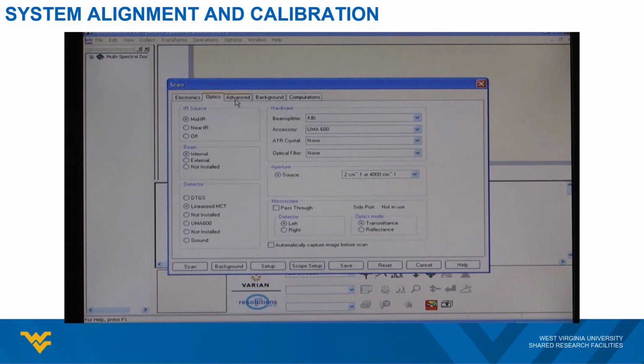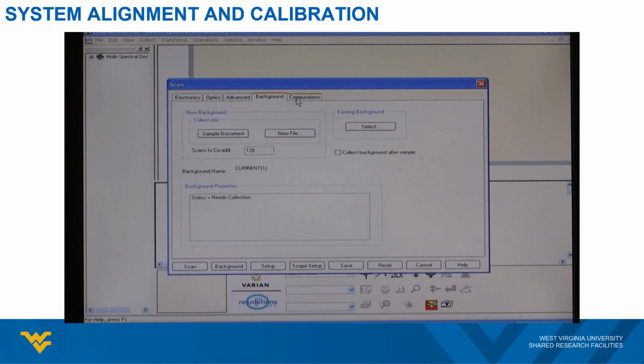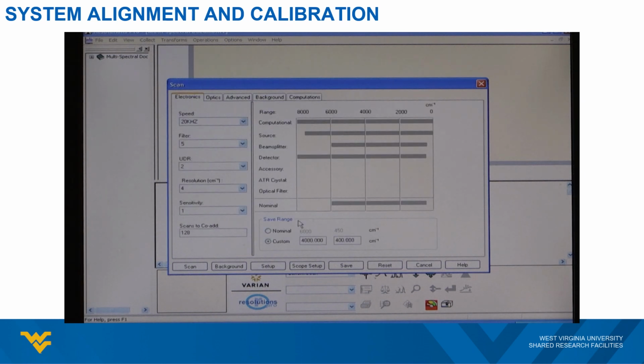Then we will need to perform the system alignment and the calibration. Here, we simply click the Setup button, which is located at the bottom of the scan window. Please remember that during this process, we will leave the ATR sample tip open as suggested earlier. After clicking the Setup button, you will see the system displaying its progress on the automatic alignment, then the automatic alignment optimization in the lower left corner. This procedure can be somewhat slow and might take around a minute, so your patience is appreciated.